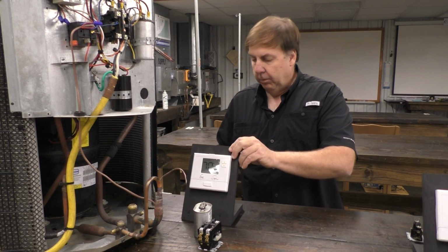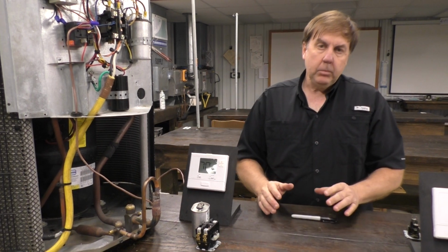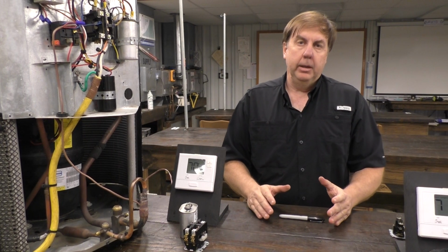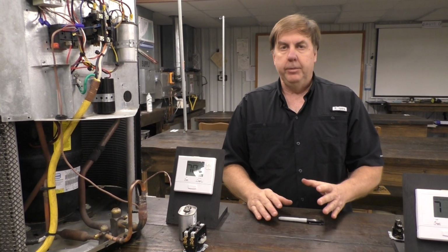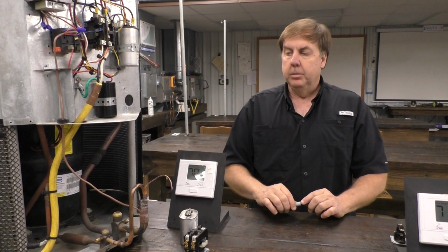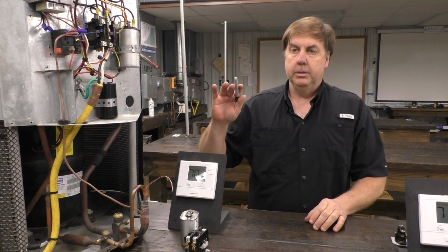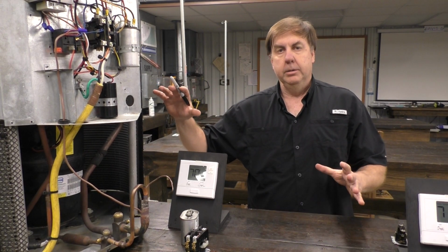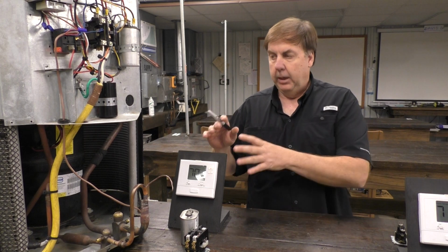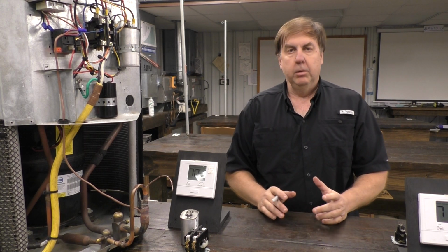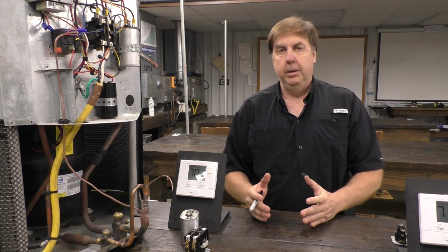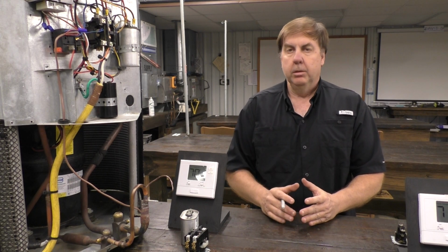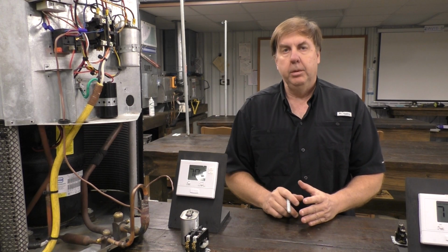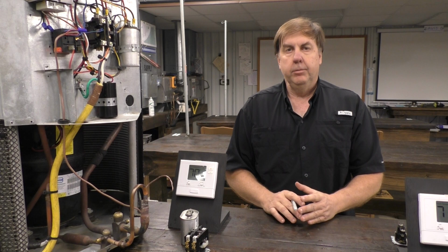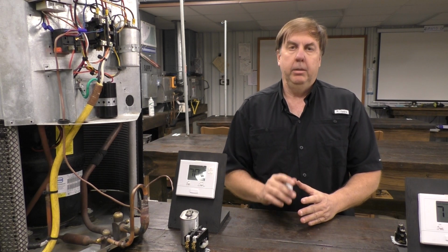So what I want you to take away from here is to be very efficient in your diagnostics. Use your knowledge of how the system works, and use things to your advantage that eliminate whole areas of the unit. If the thermostat turns the unit on, there's no reason to check for voltage to the unit—it's there. If the fan runs, there's no reason to check the contactor—it's pulled in. So use those things to your advantage, and you'll be much better at diagnosing.